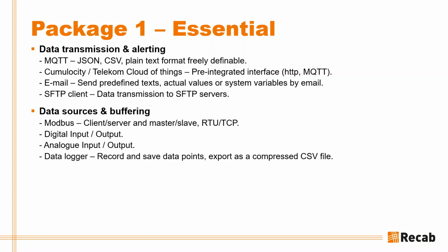And you get Modbus functionality, client/server and master/slave, so you can both get data and provide data to another control system. And you can use both RTU and TCP. And you have both digital and analog inputs and outputs. And the data logger function that I talked about is also in the essential package.